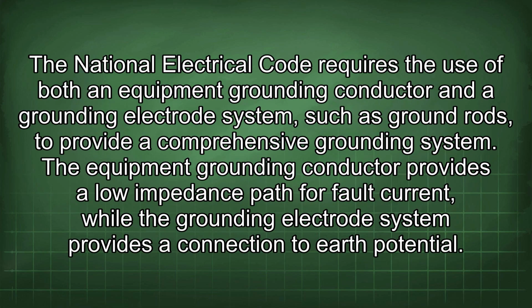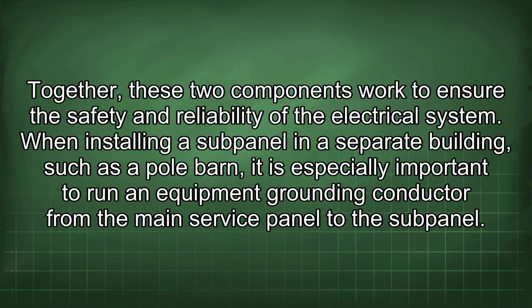The National Electrical Code requires the use of both an equipment grounding conductor and a grounding electrode system, such as ground rods, to provide a comprehensive grounding system. The equipment grounding conductor provides a low impedance path for fault current, while the grounding electrode system provides a connection to earth potential. Together, these two components work to ensure the safety and reliability of the electrical system.